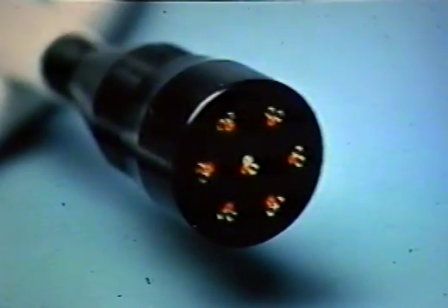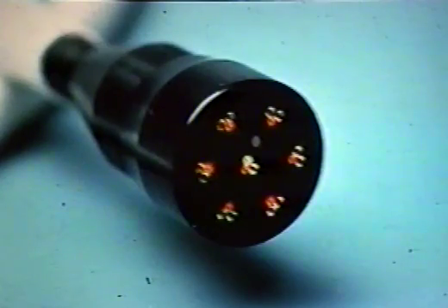Now, in order to some extent overcome this problem, we developed an averaging probe some years ago where we used not only one transmitting fiber, but altogether 7 transmitting fibers, as you can see here. The laser light is coupled down into 7 different fibers. And next to each of these transmitting fibers, we have 2 receiving fibers that pick up the light. So altogether we have 7 scattering volumes here. And this allowed us to average the data.